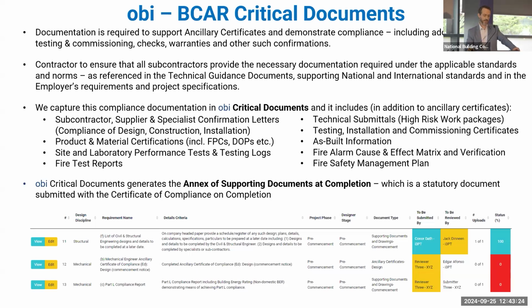We look at the contractors and subcontractors - they have to provide their documentation to say they've met the applicable standards and norms. We capture the compliance critical documents on OBI, which is basically an online dashboard or upload system like the BCMS. We look at the subcontractors and specialists, like they're providing confirmation letters to the fire engineers to say it's been installed as per the fire test report, or that it's in compliance with the fire safety certificate. The products and material certificates, the FPCs, the DOPs, the CE mark and all that good stuff. Site lab performance tests, testing logs, fire test reports - all of that good stuff.